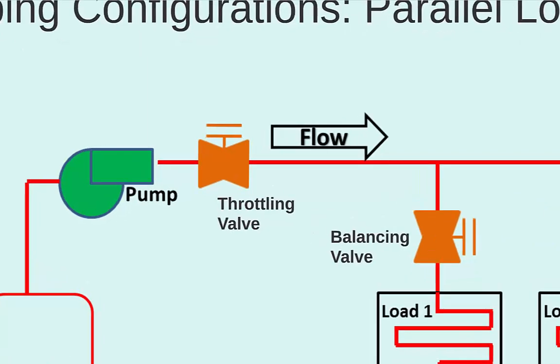If you have ever heard of a triple duty valve, that is a valve located on the discharge of the pump which serves three purposes. First, it can be adjusted during the balancing process. Thus, it is a throttling valve. Second, if maintenance needs to be accomplished on the pump, the triple duty valve can serve as an isolation valve. And lastly, the triple duty valve can serve as a check valve to ensure that at no time water is allowed to flow backwards through the pump.